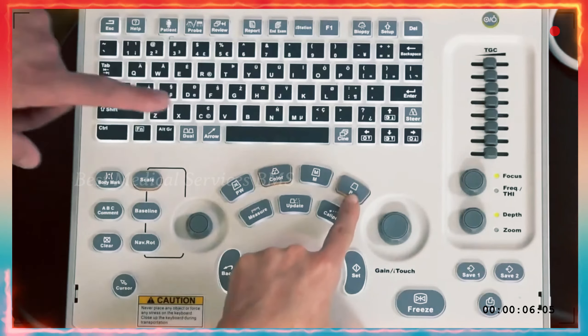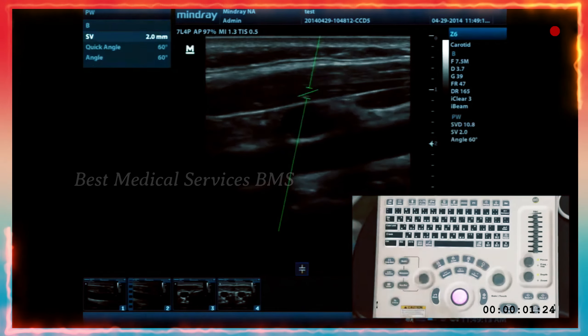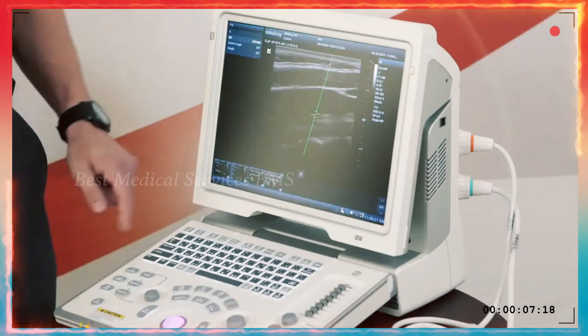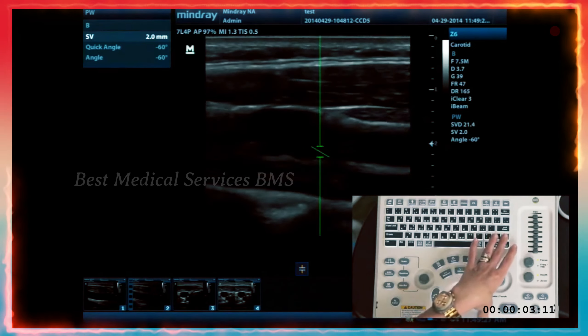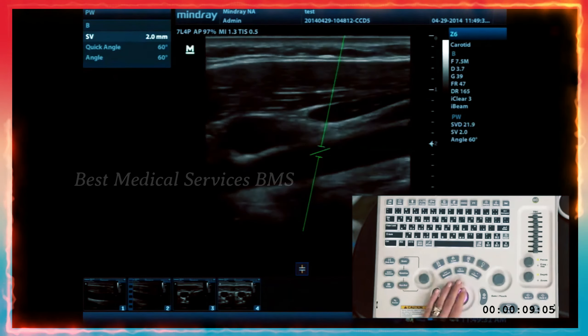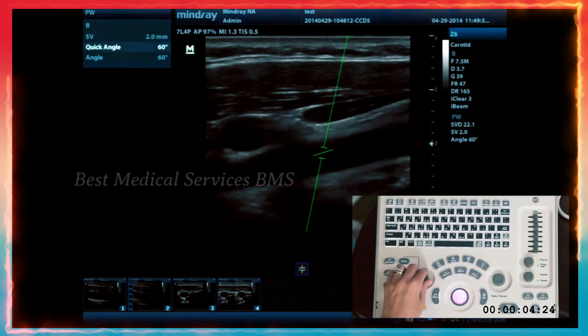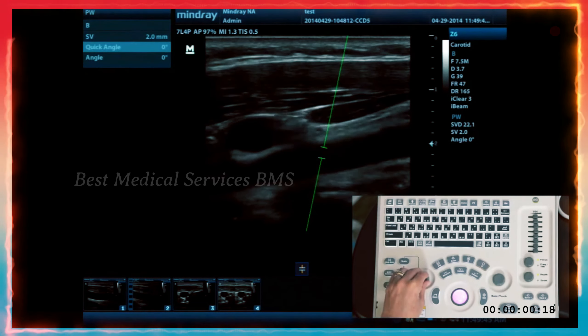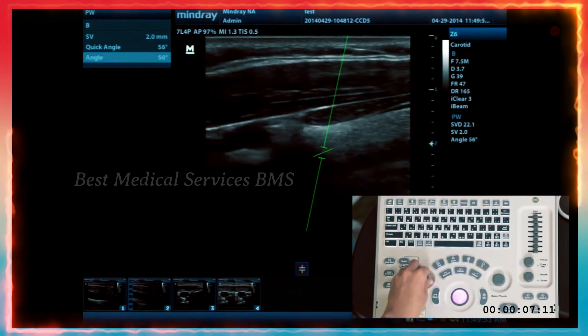Now we'll talk about pulse wave Doppler. When you hit pulse wave Doppler, you bring up your cursor with your sample volume, and your angle is already set for you. The steer quick key goes left, right, and vertical. The angle is automatically set at 60 degrees to be parallel with the vessel walls. Your rotary navigation will allow you to change your quick angle, going between 60, -60, and 0. Pressing again and scrolling down to angle gives you fine angle adjustments one degree at a time.